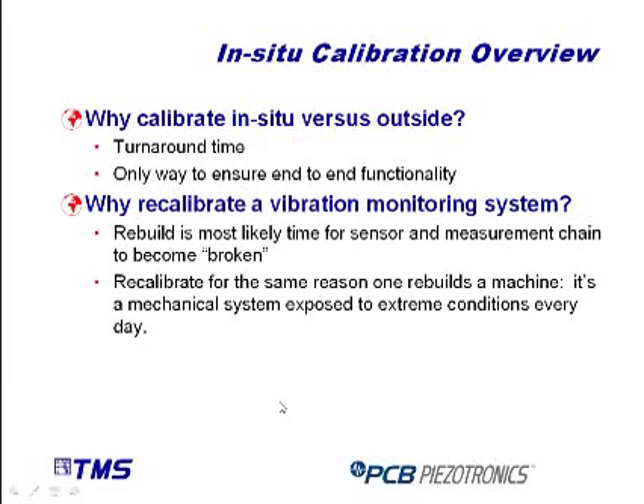This allows for a confirmation of end-to-end functionality as well as reduced turnaround time versus sending a transducer out of the facility to a metrology lab. The rebuild time for the machinery is most likely the time when that sensor and measurement chain will become broken, whether it's a damaged cable or a damaged transducer. That's when it makes the most sense to provide this calibration, provide this verification to the end-to-end measurement channel.